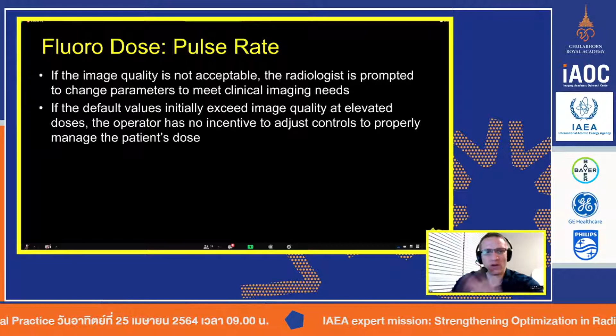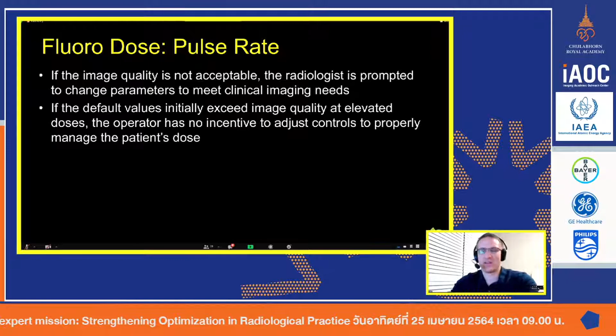If you set the default at the highest value, you're rarely going to have an operator or a radiologist walk in and say, oh, this image quality is way too good, I want to reduce my dose. That rarely happens. So oftentimes we'll set it at the minimum, and then we give them 2 or 3 options, whatever your system allows, to increase the pulse rate, or in other words, the dose to the patient.